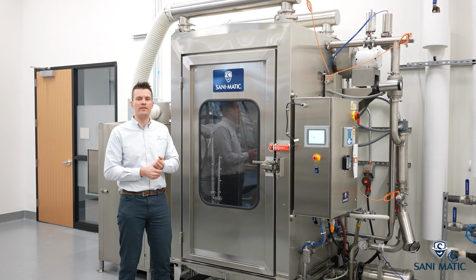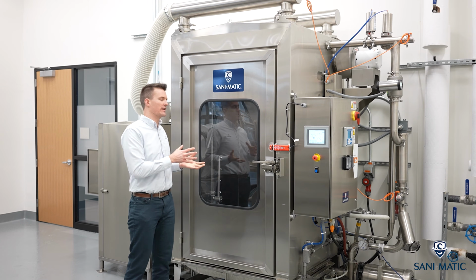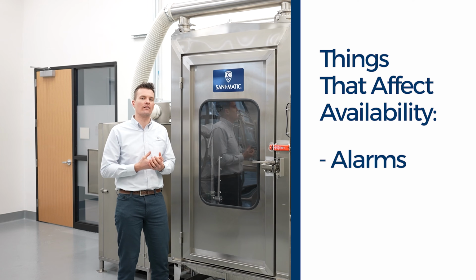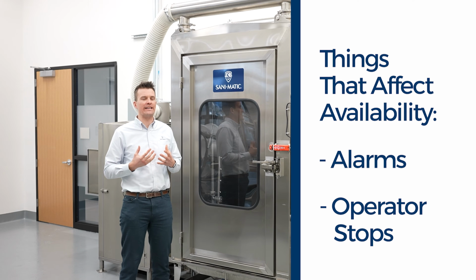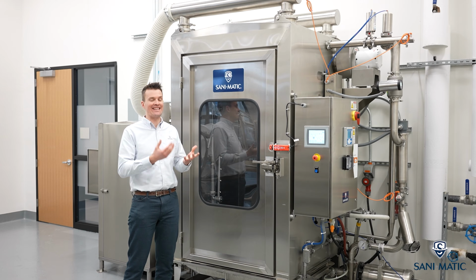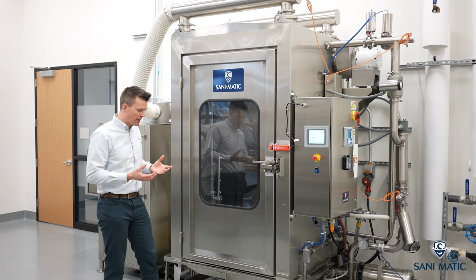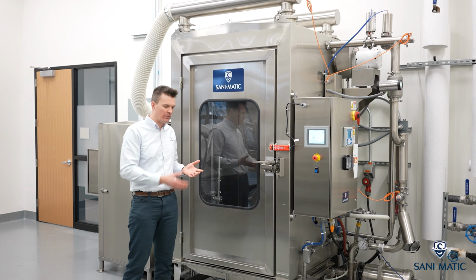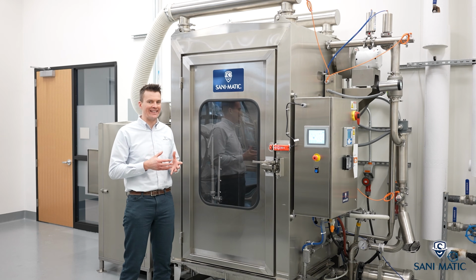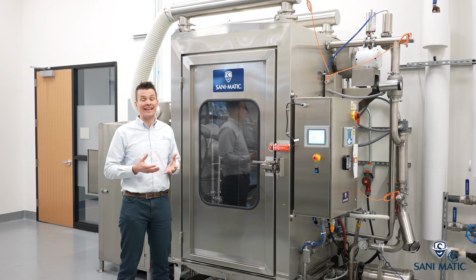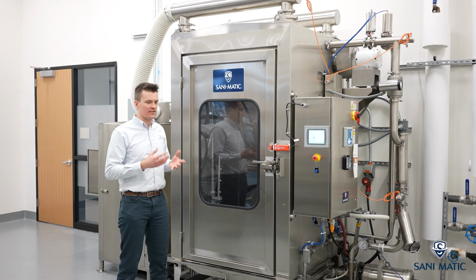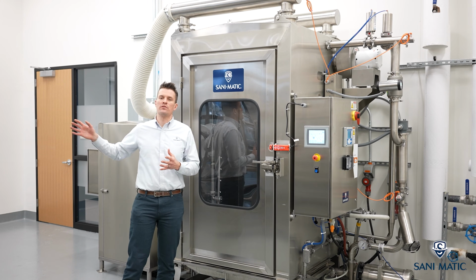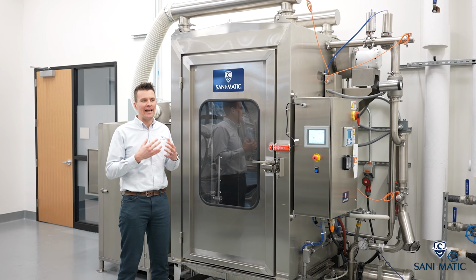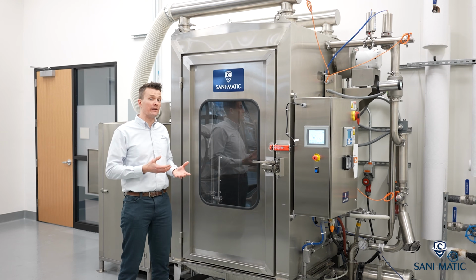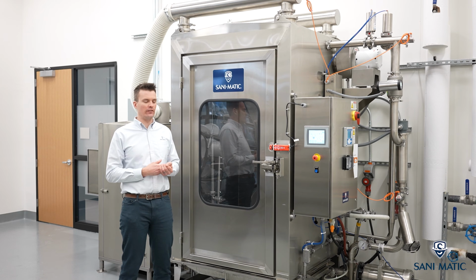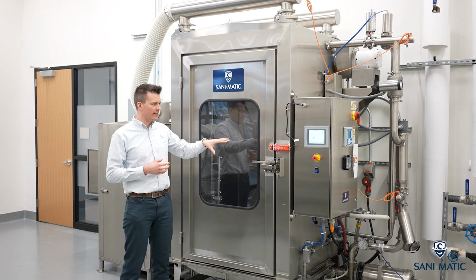So first, how do we define availability for a cleaning system? For us, two things impact that: alarms and operator stops. So we're really defining when your system is available when you're intending to clean. If I have my system up and running and I'm doing an 8-hour shift and I'm going to clean throughout that, we want that system to be up and running and not sitting idle because an operator stopped it, or because it's been alarmed out and the operator is doing another task and hasn't come back to look at it. Anytime the system is in that state where it's not running but could be, that's going to impact our availability.